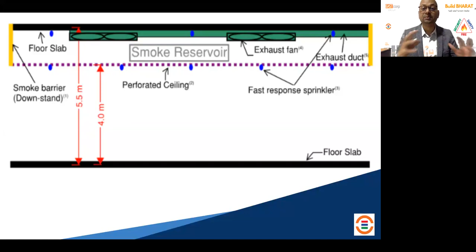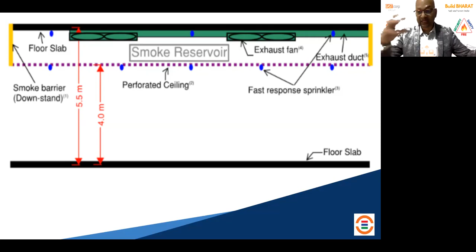So you have fast response sprinklers at the ceiling void area, and you have fast response sprinklers at the room void area at a very specified distance. That's how you manage your smoke in such a way that it will not only accumulate, but it will be taken out using the exhaust fans. You also have a shaft, which is the exhaust duct, and that exhaust duct will take the smoke out of the building.